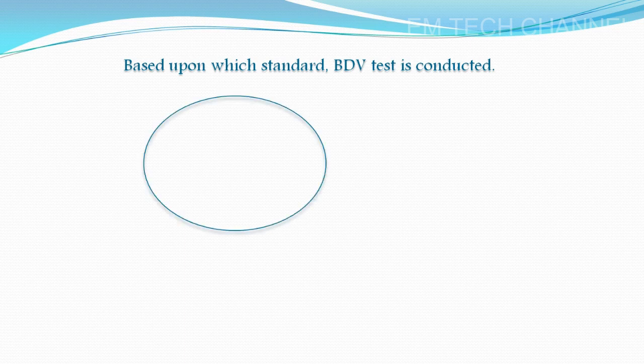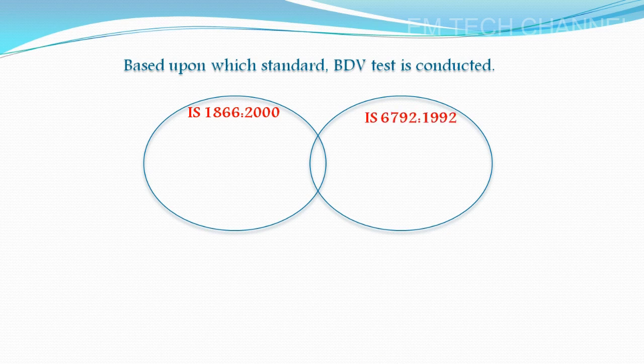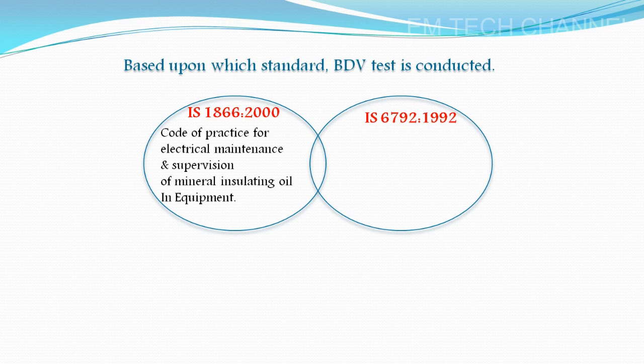It is carried out based on two Indian standards. One is IS 1866 and the second is IS 6792. IS means Indian Standard. The year that comes after the standard number is the revision year. IS 1866 is titled Code of Practice for Electrical Maintenance and Supervision of Mineral Insulating Oil in Equipment, and IS 6792 is the Method for Determination of Electric Strength of Insulating Oil.